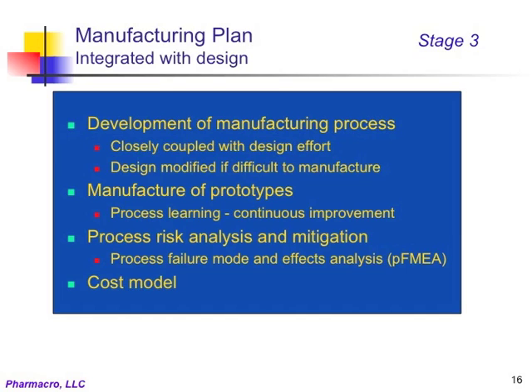Prototype manufacturing for testing involves learnings that are implemented in the further development of the manufacturing process. At this stage, it is also important to conduct process risk analysis in the form of Process Failure Modes and Effects Analysis, or PFMEA, which involves a process similar in concept to the design FMEA discussed earlier. The intent is to identify and mitigate high risks in the manufacturing process that could lead to safety, reliability, and efficacy issues in the performance of the device.